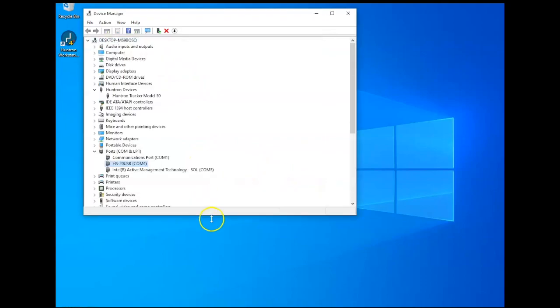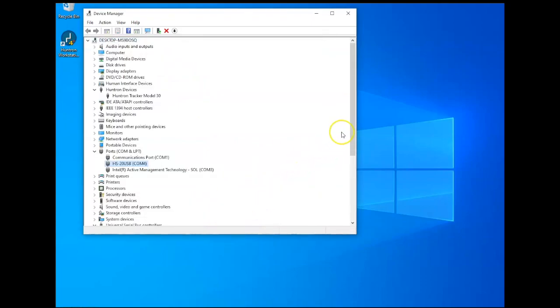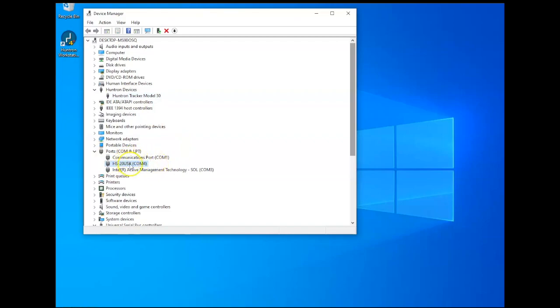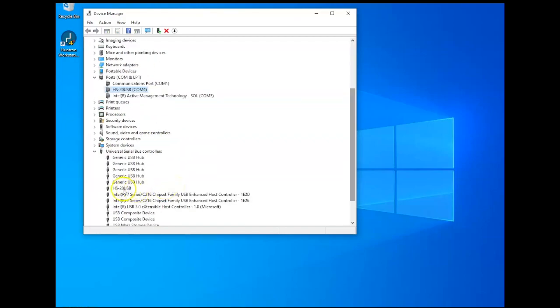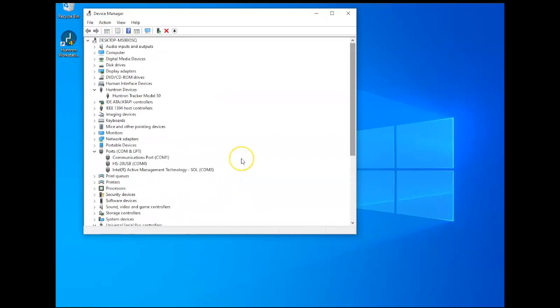So when these are installed successfully, you'll have a Huntron Devices folder where the Tracker Model 30 is located. And notice in the Ports category, my HS20 USB is mapped to COM4. I need to know that. So I'll make note that the COM4 is where my motor controller is mapped to at this point.